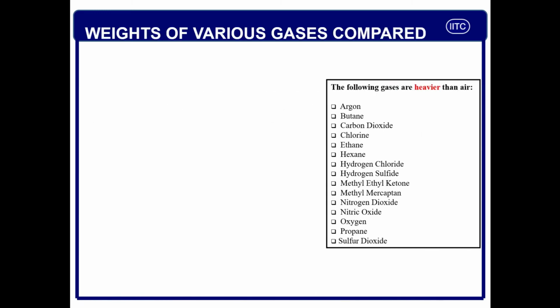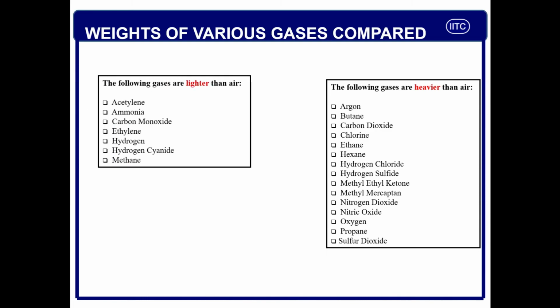What are the various gases compared? If you see in the left side block, there are gases which are lighter than air: acetylene, ammonia, carbon monoxide, ethylene, hydrogen cyanide, methane. These gases are lighter than air. On the right side, you can see a number of gases which are heavier than air: argon, butane, carbon dioxide, chlorine, ethane, hexane, hydrogen chloride, and others.